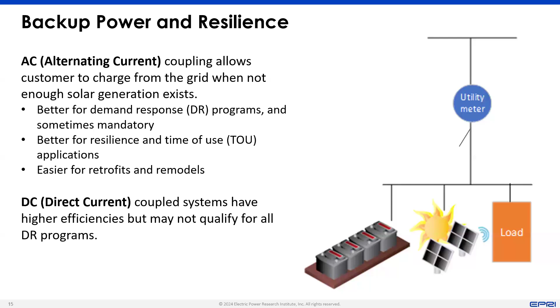It also allows you to use it for time of use applications, for example, when you wouldn't otherwise be able to charge that battery on a cloudy day. The advantage to DC coupled systems is that your efficiency is higher because you don't have that inverter between the solar system and the battery, which does hurt efficiency a bit. In the past, we saw a lot more DC connected systems for tax purposes in particular, but those rules have been changed, and so we are seeing many more AC connected systems. That's kind of the way to go. It allows the customer the most leeway to use the battery as they'd like and take advantage of different programs and opportunities offered by their utility or others to earn money for the use of their battery on the system.